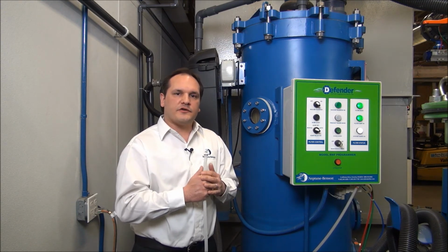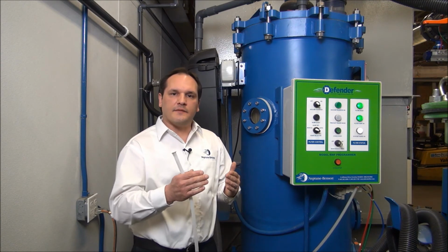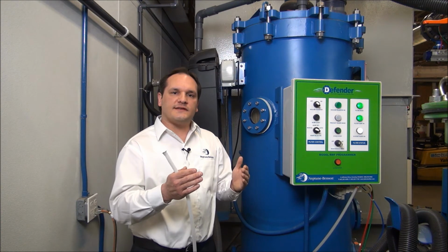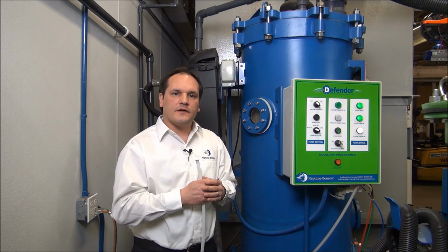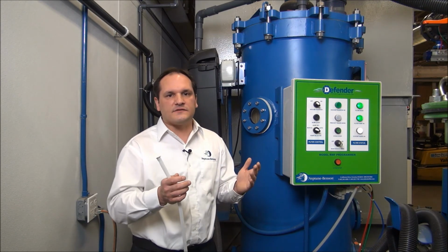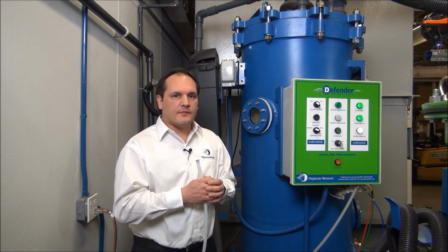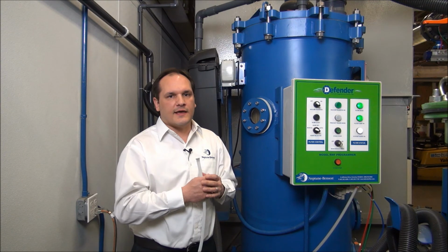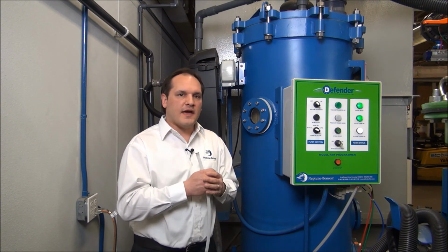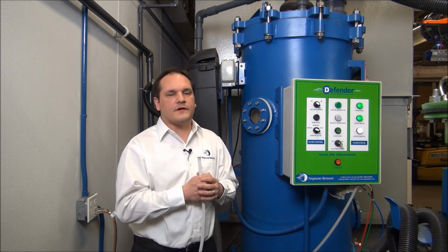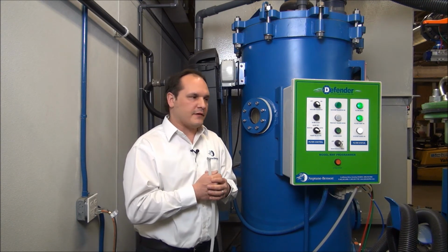For example, in a traditional high-rate sand filter, the filter will get dirty as soon as you turn it on. Once the pressure differential reaches that 10 psi greater than your startup, it means it's time to backwash that sand filter, thus sending approximately tens of thousands of gallons of water to waste each and every time. With the Defender filter being able to pre-coat it and bump it on a daily basis, we're extending the filter cycle from, say, every day, every other day of backwashing a sand filter to approximately once a month of changing the media on the Defender filter.